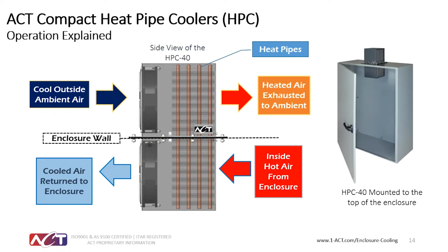of the cabinet. The lower half of the sealed ACT HPC heat pipe heat exchanger is on the inside of the cabinet. There, the heat pipe's heat transfer working fluid evaporates in the hotter inner cabinet environment. The internal heat pipe vapor flows through a sealed dividing plate to the outer part of the cabinet housed by the ACT HPC, then condenses and flows back to the inside of the cabinet as a liquid, aided by gravity.